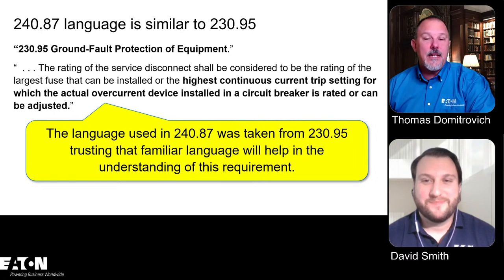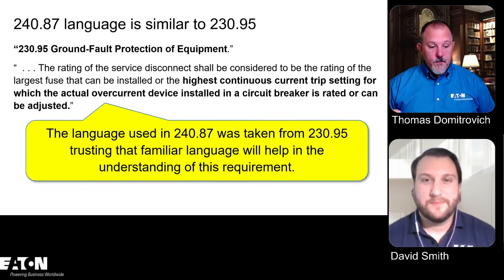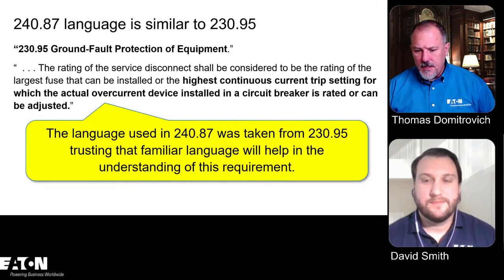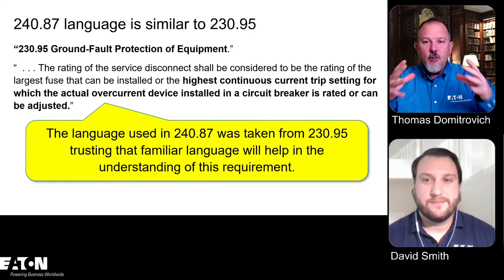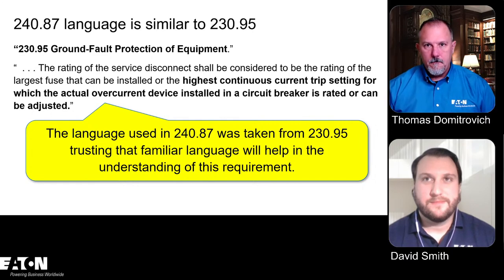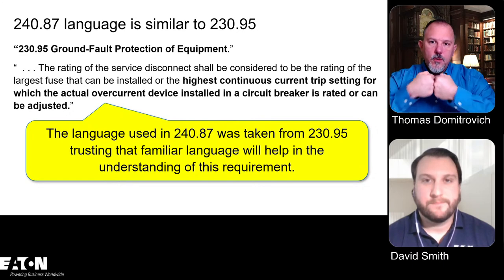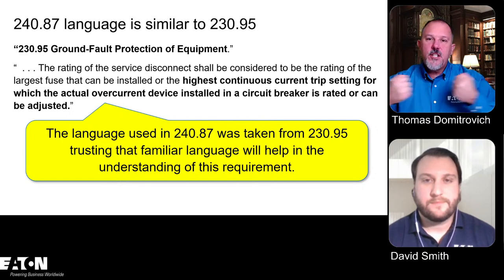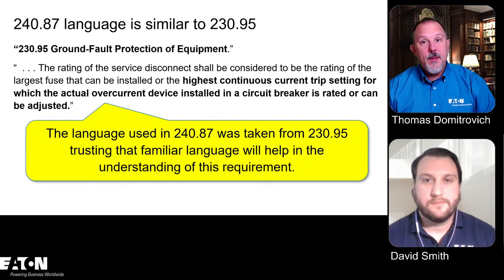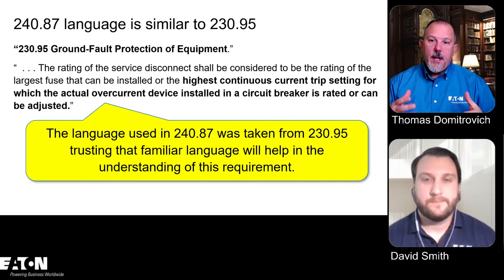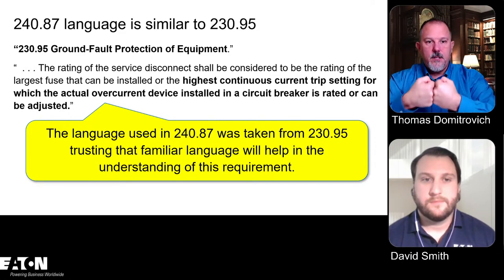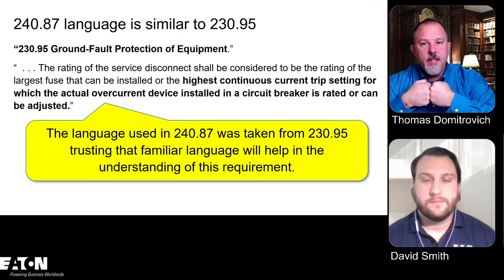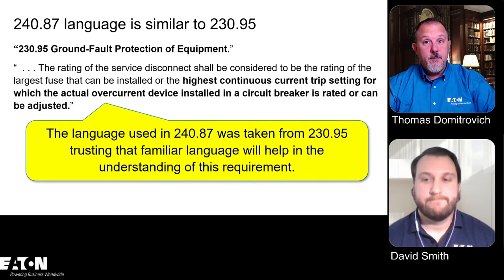So same thing with an insulated case circuit breaker. What happened was years ago, I think it was Westinghouse at the time, needed an intermediate breaker before the power circuit breaker. They wanted a breaker that could hold its contacts closed much longer and went to a higher ampere rating than your standard molded case circuit breaker, which goes up to 2,500 amps. Sure. And the reason they needed that was when you're trying to selectively coordinate breakers, you want that upstream device to hold those contacts closed under those higher fault currents so the downstream device does its job.